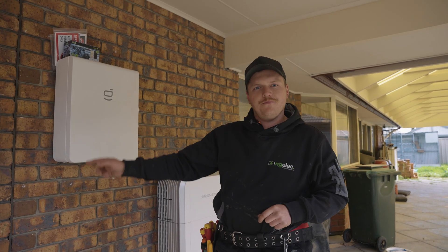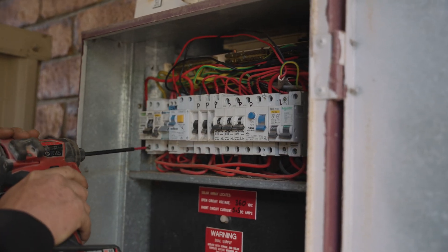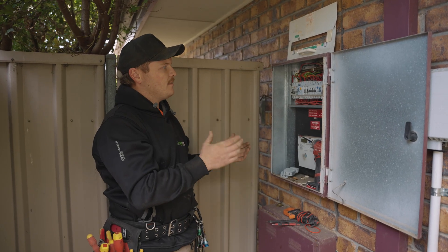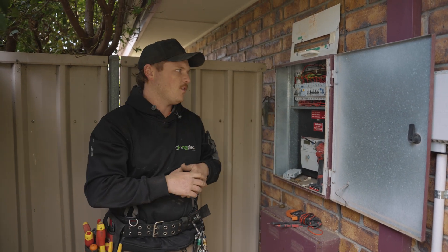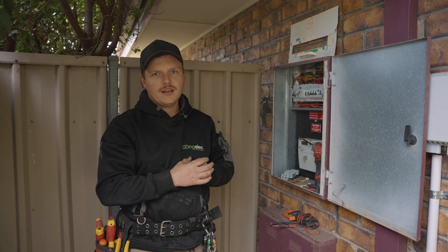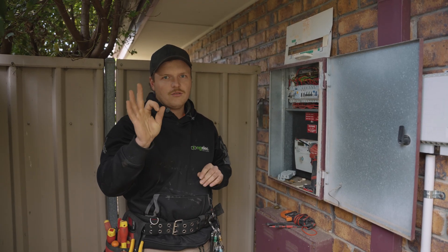As you can see, this switchboard and its switchgear are pretty well completely outdated. We've opted for a whole home backup for this house, so we're going to have to upgrade the whole switchboard completely — ripping all of this out, reinstalling Hager RCBOs for each individual circuit, and making sure she's all up to scratch.